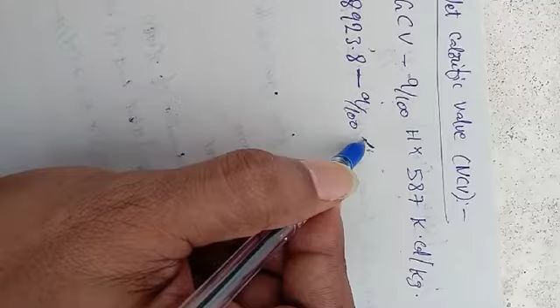Now we are going to calculate here low calorific value. So that is called net calorific value, NCV. So now here NCV is equal to GCV minus 9 by 100 H into 587 kilocalorie per kg. Now here substitute these values. 9 by 100 into 8 into 587. The units are must. Okay, now we calculate this, we'll get kilocalorie per kg. Okay, this is the answer for net calorific value.